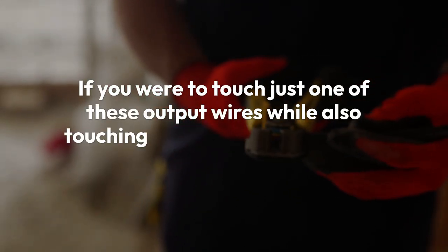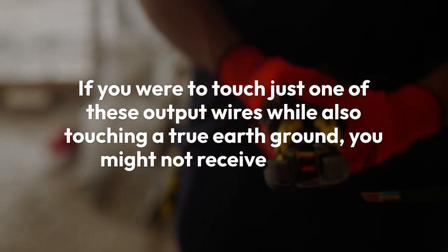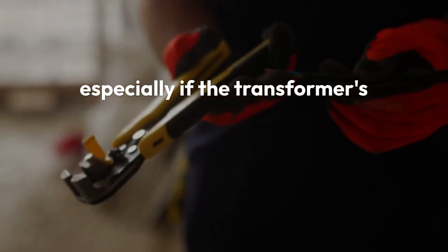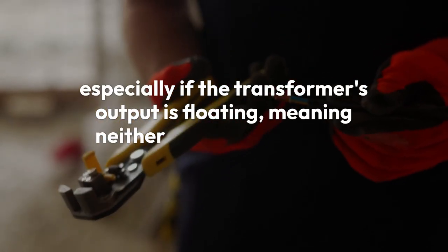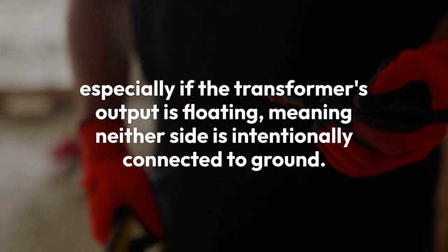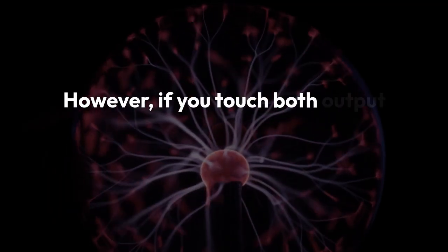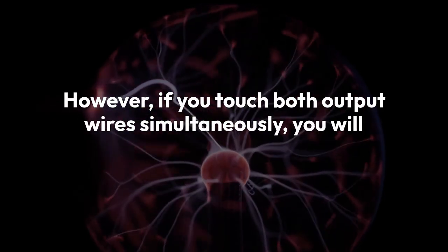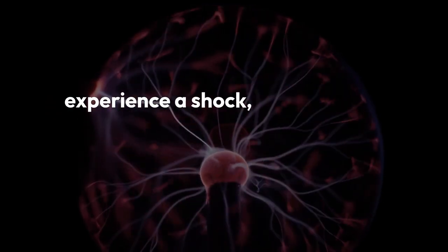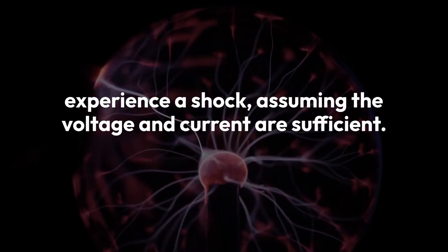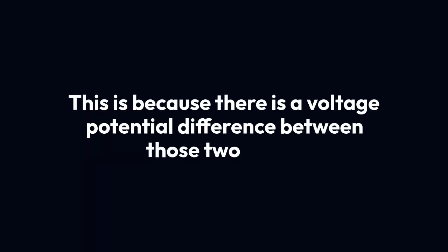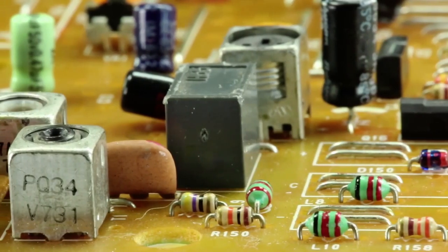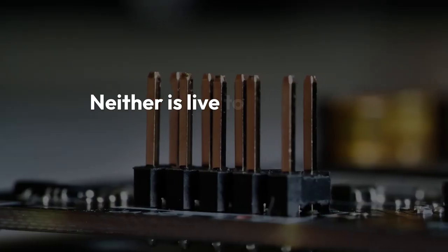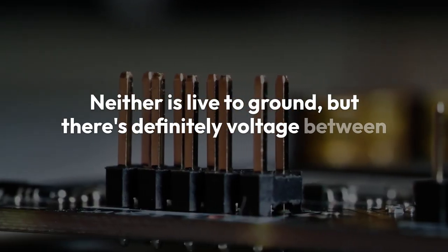If you were to touch just one of these output wires while also touching a true earth ground, you might not receive a shock, especially if the transformer's output is floating, meaning neither side is intentionally connected to ground. However, if you touch both output wires simultaneously, you will complete the circuit and experience a shock, assuming the voltage and current are sufficient. This is because there is a voltage potential difference between those two wires. It's like the two terminals of a battery. Neither is live to ground, but there's definitely voltage between them.